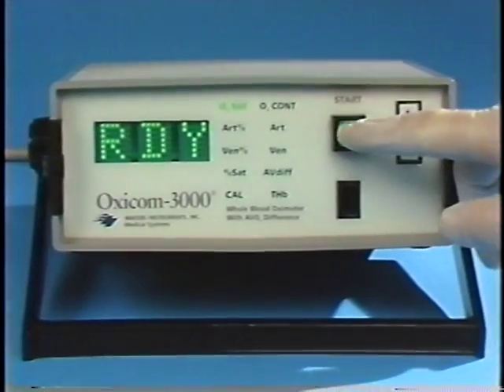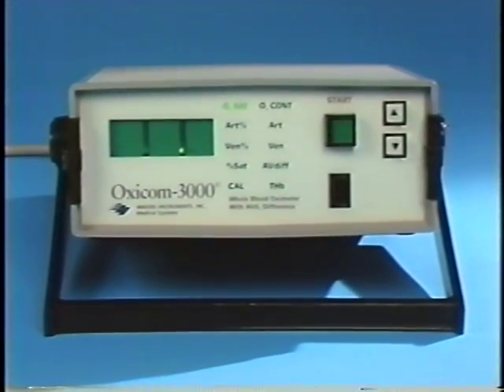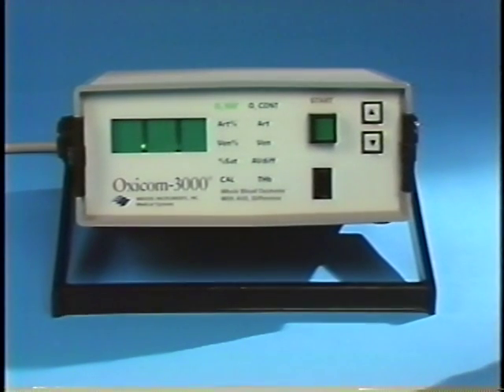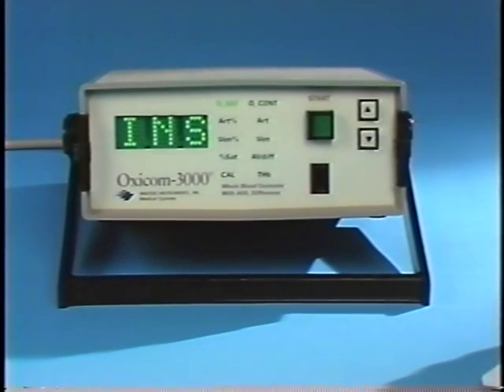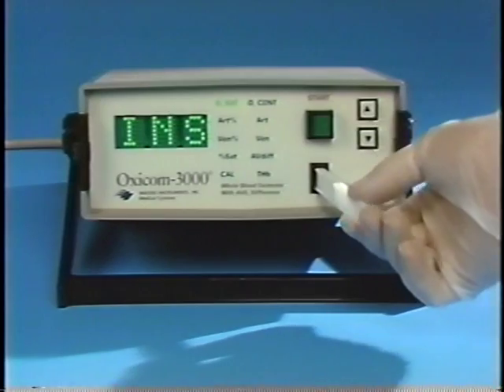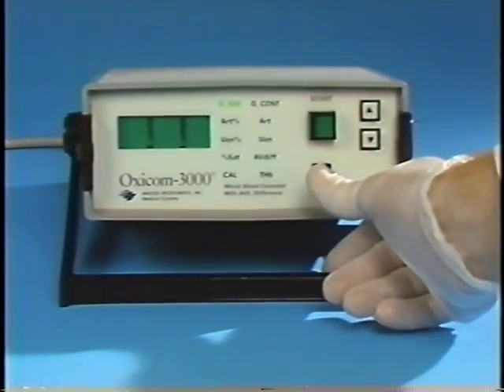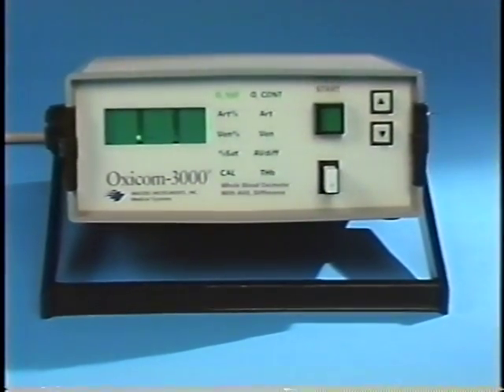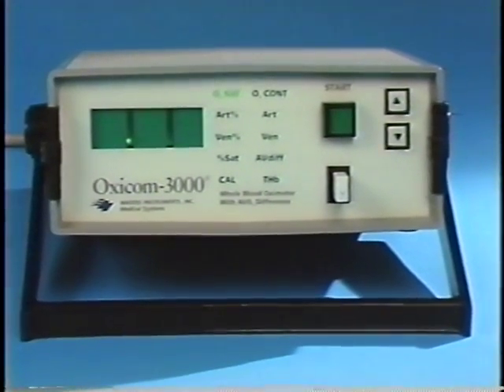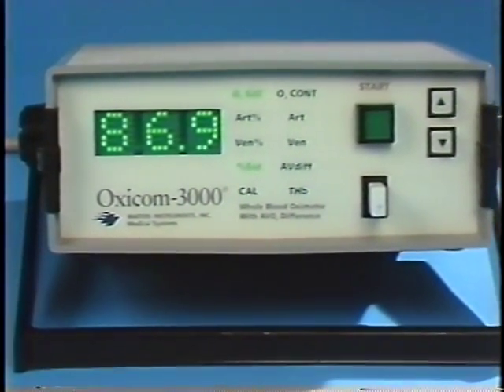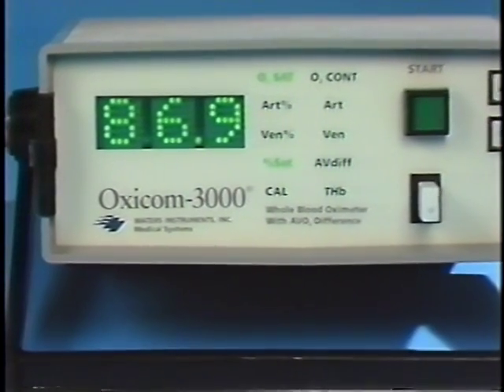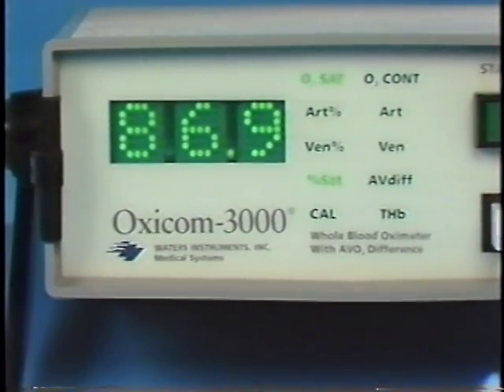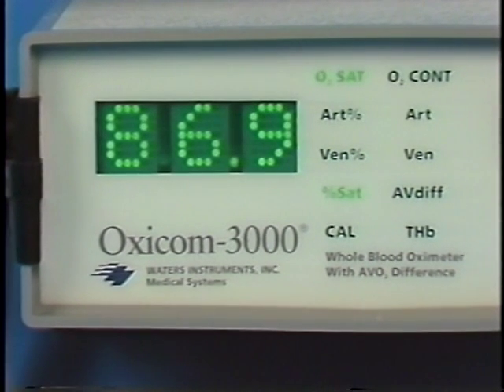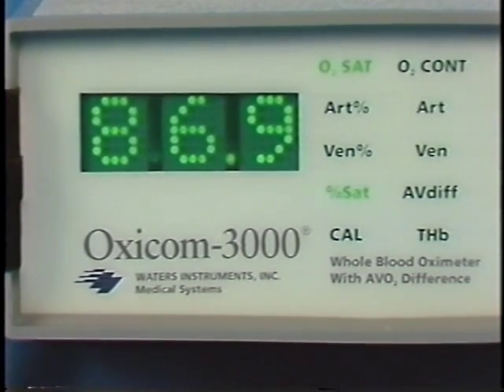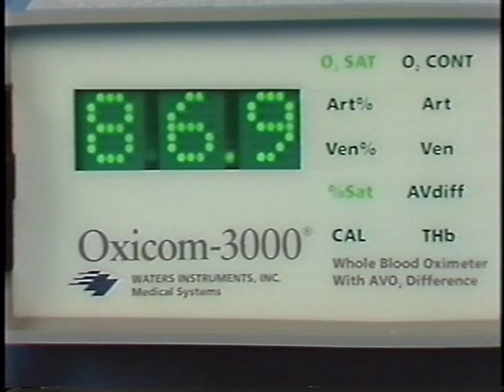Every morning, after the timed 15-minute warm-up period has elapsed, insert the stick into the sample chamber. Because the Delrin stick has a known optical property, any change greater than plus or minus 3% indicates recalibration is required. By following this daily calibration verification and the recommended accuracy checks, the Oxicom 3000 will give you many years of trouble-free, accurate saturations. Refer to the manual for complete details on all subjects as well as troubleshooting and maintenance.